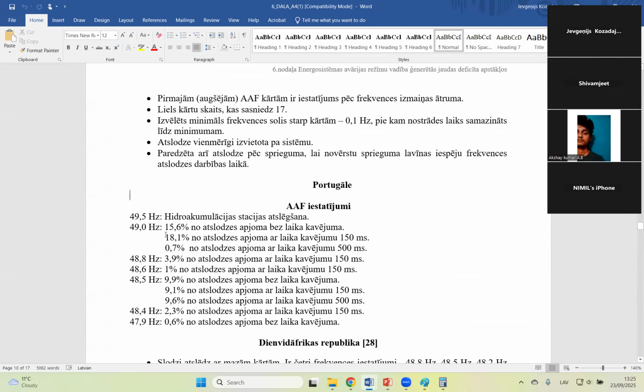For example, this is Portugal. The first stage is at 49.5 hertz, and at this stage, all the hydro pump power plants, where you could pump the water up in pump mode and another time convert this water to electricity. So if you have a hydro pump power station in pump mode, then for the first stage you disconnect this pump mode.